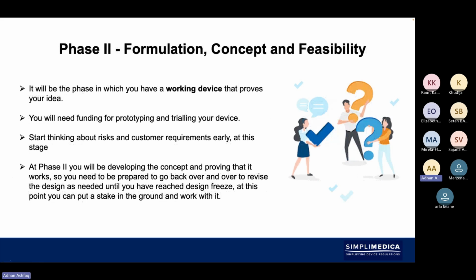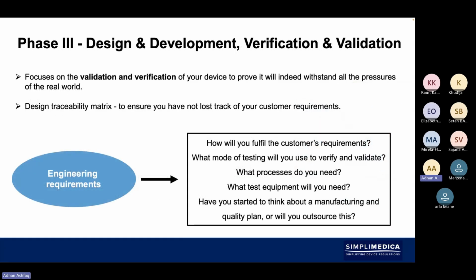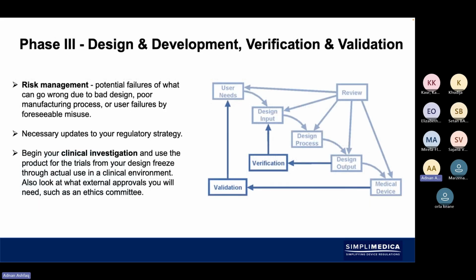So when we're looking at the formulation, concept and feasibility, that's when you have a working device. You might need funding at that point for prototyping and trialing your device, start thinking about risks, and then move into conceptualizing and then verification and validation. Making sure that you've got customer requirements. Have you followed through the customer requirements? Do you have a traceability matrix? Look at the verification and validation needs. Look at what it needs for withstanding real world pressures. You might have some things that are outsourced. You need to consider what test equipment you need in-house if you're going to test it. Otherwise, all your activities might be outsourced. You might need to have a subcontractor manufacturer in place. Then you need to have supplier verification controls in place also.